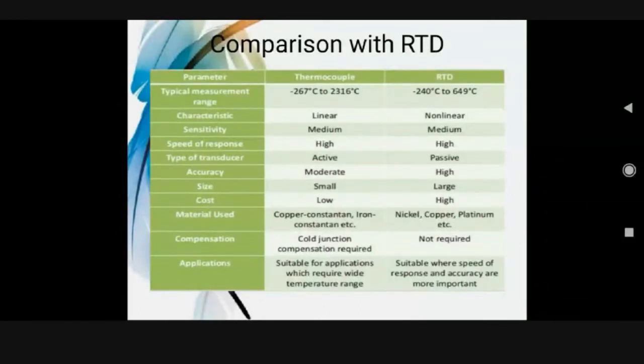Sensitivity of thermocouple is medium and same as thermocouple, RTD sensitivity is medium. Speed of response of thermocouple is high and same as thermocouple, RTD is high. The type of transducer is active for thermocouple and passive for RTD. Accuracy of thermocouple is moderate and accuracy of RTD is high. The size of thermocouple is small. Size of RTD is large.